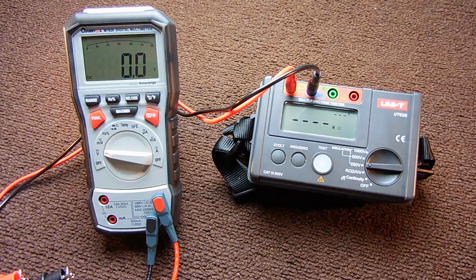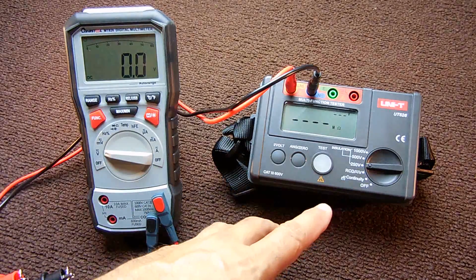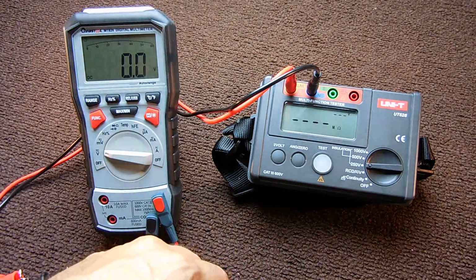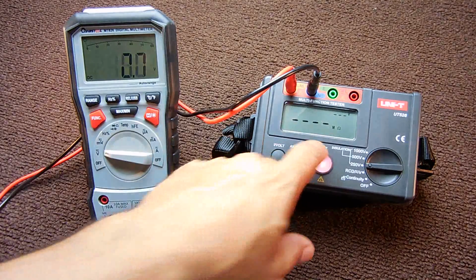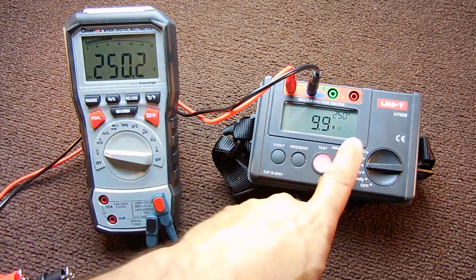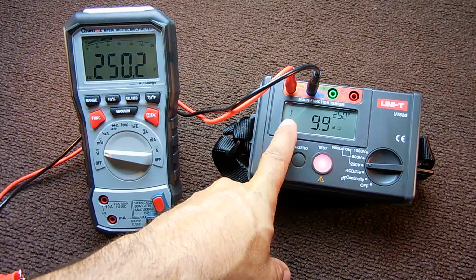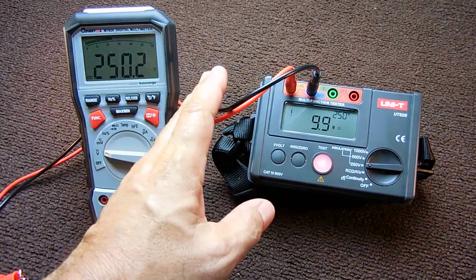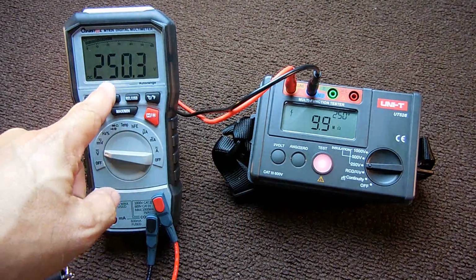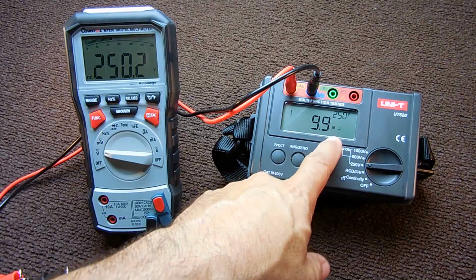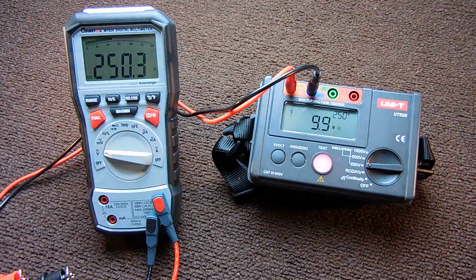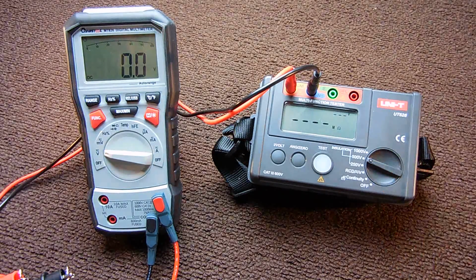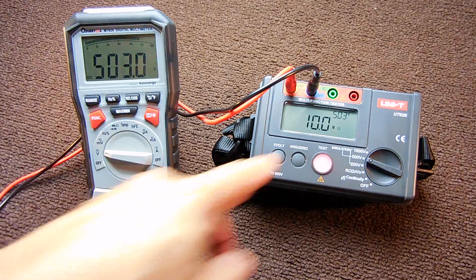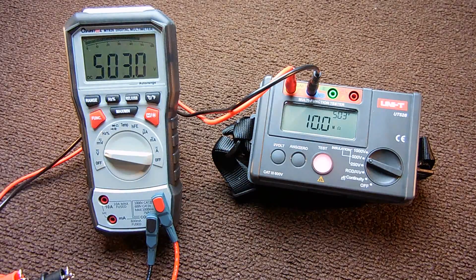Now that it's connected up, what we're going to do is push the test button. The test will remain active until I push the test button again to turn it off. Over here, 250 volt test voltage. You can see this lightning bolt flashing, which means stay away from the wires as long as that's flashing. 250 and 9.9 megohm. That's the impedance of this meter. Push to stop. Now let's push it to 500. Try it again. We got 503 volts, 10 megohm.